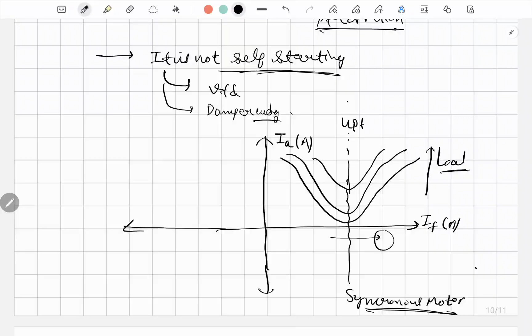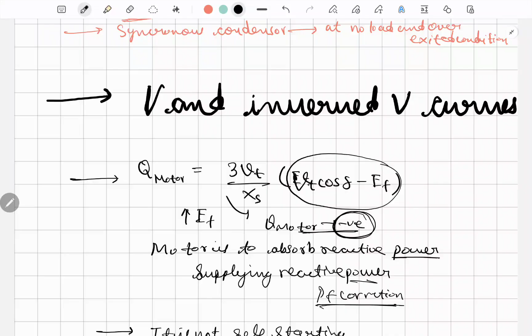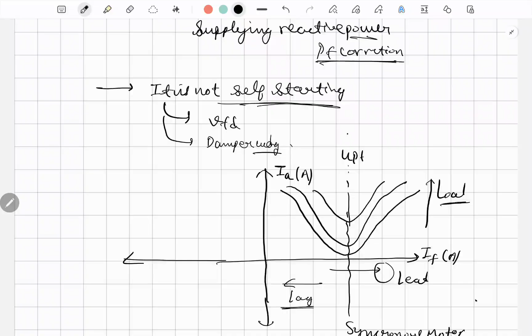If we increase the excitation, going this way, the excitation increases. As we saw previously, increasing excitation makes the motor's reactive power negative, and negative reactive power means the power factor will be leading. So we get a leading power factor in this region, and a lagging power factor in the under-excited region of the synchronous motor. This was the V curve.